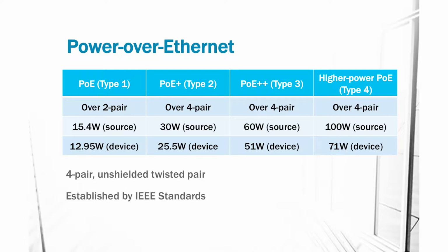Your type 1, 15 watt, uses just over half of the pairs, and this bottom line is the delivered power. If you have a 295-foot cable, there's going to be voltage drop, so this is the max watts we can guarantee at the end of that permanent link. There's supposed to be a closed parentheses here too, so pardon the typo.